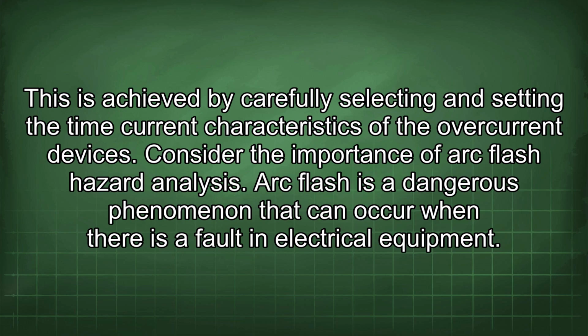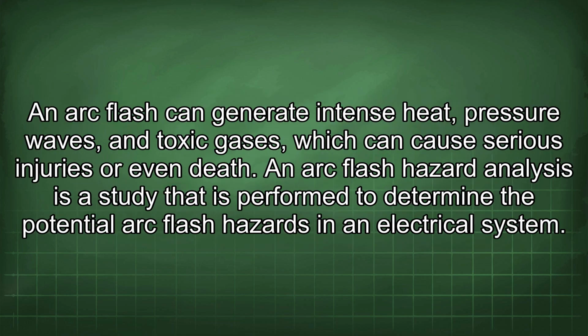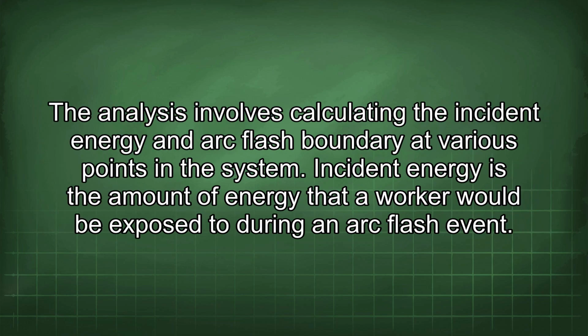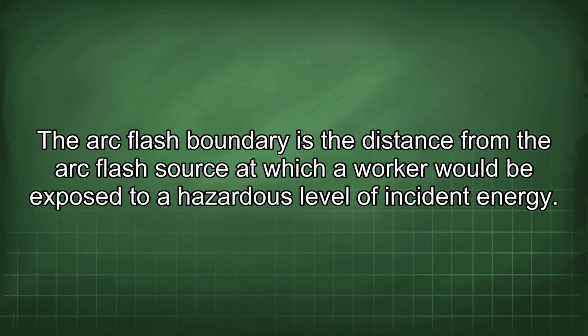Consider the importance of arc flash hazard analysis. Arc flash is a dangerous phenomenon that can occur when there is a fault in electrical equipment. An arc flash can generate intense heat, pressure waves, and toxic gases, which can cause serious injuries or even death. An arc flash hazard analysis is a study that is performed to determine the potential arc flash hazards in an electrical system. The analysis involves calculating the incident energy and arc flash boundary at various points in the system. Incident energy is the amount of energy that a worker would be exposed to during an arc flash event. The arc flash boundary is the distance from the arc flash source at which a worker would be exposed to a hazardous level of incident energy.